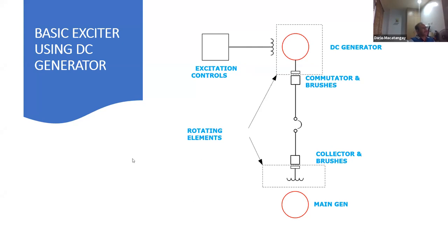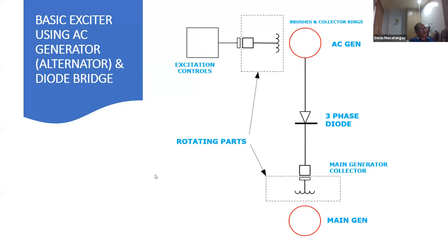Now we go to the second type of the excitation system, using a diode bridge. Before, we had a DC generator. Now we're replacing the DC generator with an AC generator. With this AC generator, we're using brushes and collector rings here. You can see that the field used for the AC generator is rotating with the field of the main generator. And this bridge here, which is a three-phase diode, usually a six-pulse, thyristor type, is stationary here, all right?